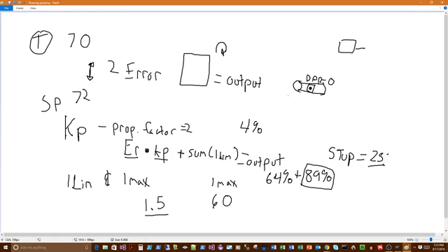So what we're looking at here, I'm going to go through this one last time before I move off this topic. You've got your process variable, PV, also known as the input variable, and you've got your set point, SP. The difference between the two is the error: set point minus PV equals error. Then you've got your factor for the proportional side of your loop, which is the factor that times the error - error times proportional factor - plus the sum of your Ilim. That's the integral time piece, so proportional is the proportional piece and this is the integral time piece.